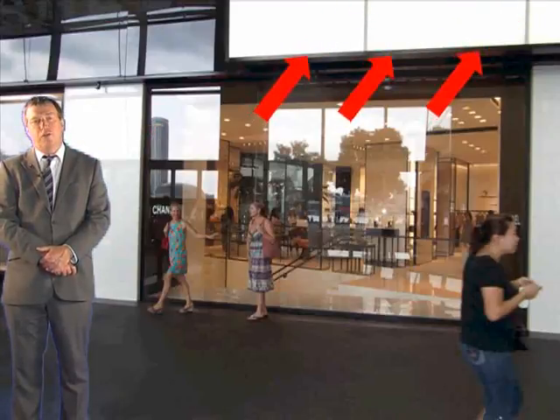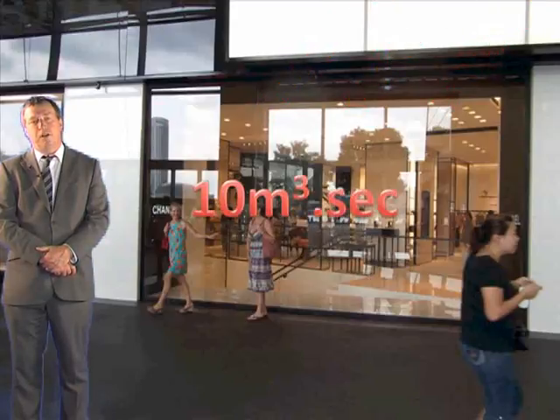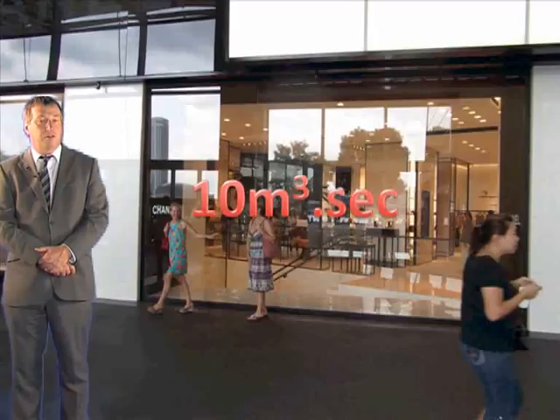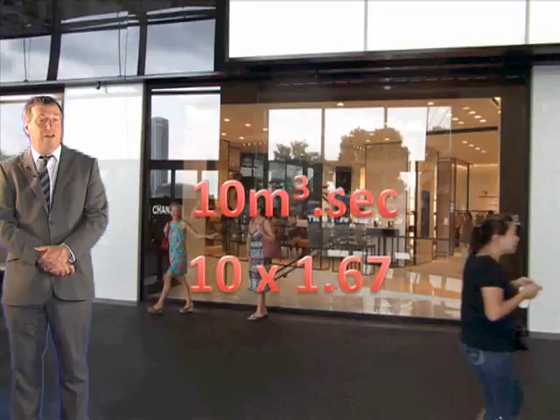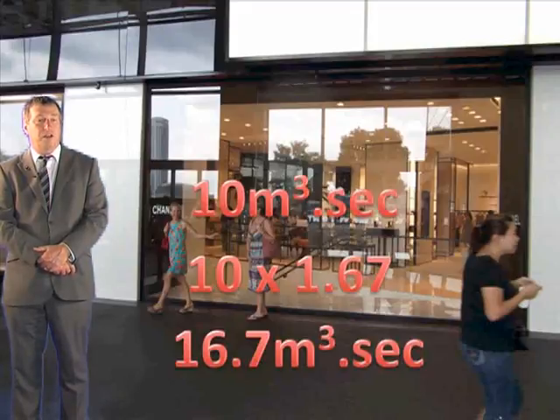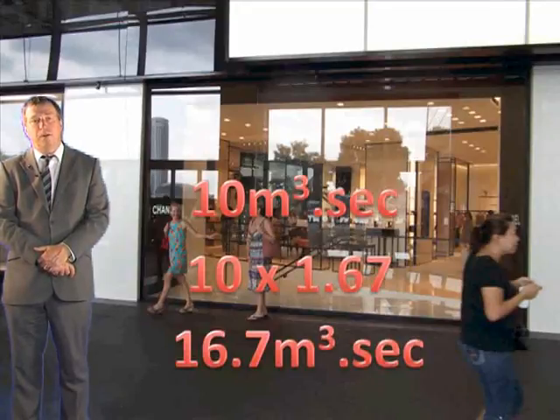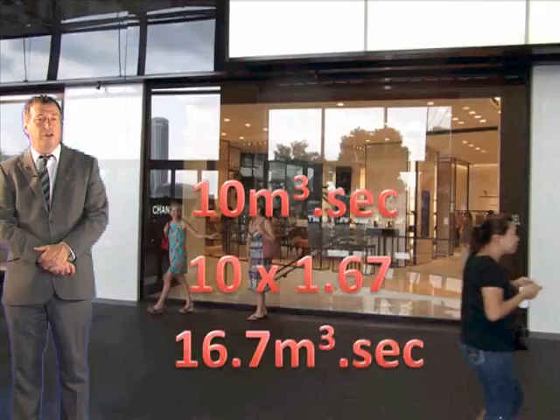In other words, if we've calculated that there are 10 cubic meters per second of smoke moving towards the slot, and we don't want the smoke to pass the slot, we should extract from the slot at a rate of 10 times 1.67, which equals 16.7 cubic meters per second. In this way, the 10 cubic meters per second of smoke will get drawn into the slot along with an additional 6.7 cubic meters per second of fresh air.